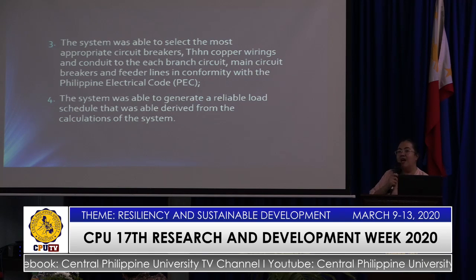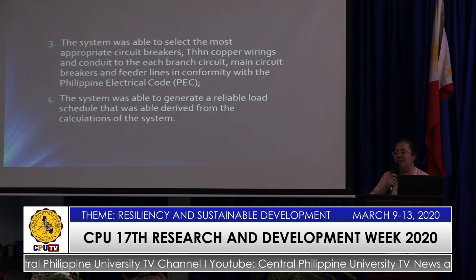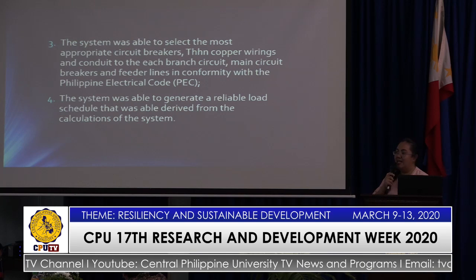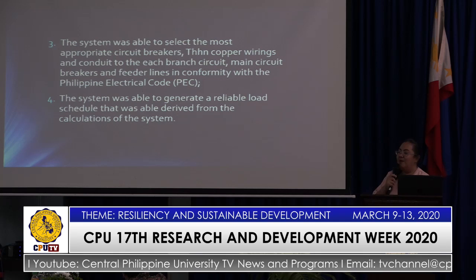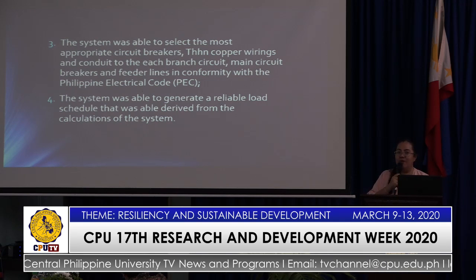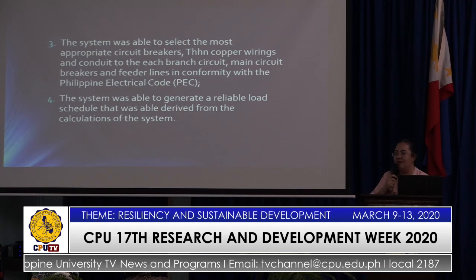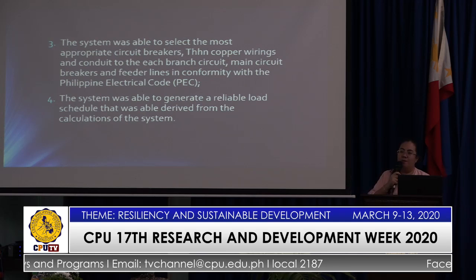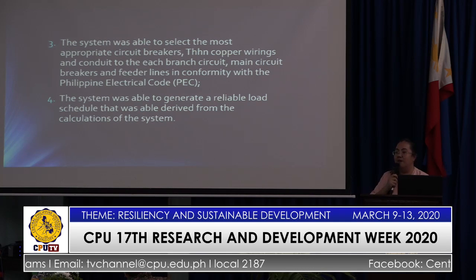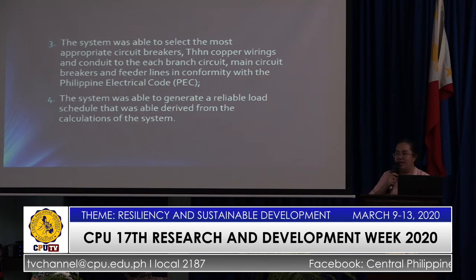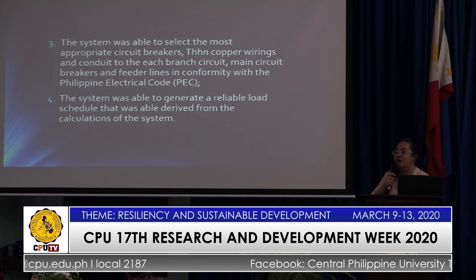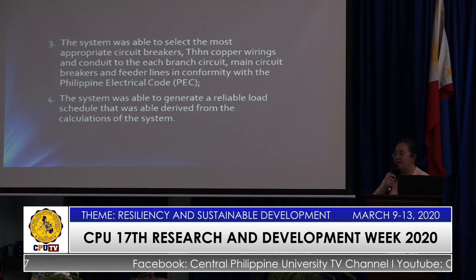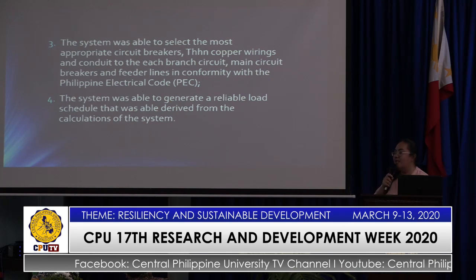It can assign a higher value, but the problem is that a higher circuit breaker or bigger wires means more expensive. The difference between the sizes of circuit breakers is not just about 1,000. Sometimes the difference would be 10,000, 20,000. And sometimes it could go up to a difference of 1,000,000 in terms of the wires. So as electrical engineers, as design engineers, you have to create a balance between safety and cost. That's why I chose the best fit algorithm.